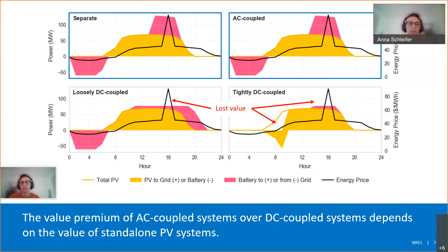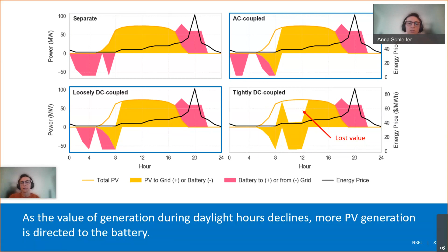And then in the case of the tightly DC coupled system, even more value is lost because the battery has to charge from the PV array instead of from the grid. And sorry, the negative reflects charging of the battery and the positive reflects anything to the grid. So then as the share of PV generation increases, you can see that higher price hours are pushed outside of daylight hours. So now both the AC coupled and loosely DC coupled systems charge later in the morning and discharge in the evening. So now these two systems provide similar value. And then the tightly DC coupled system still loses some value because it has to charge more from the PV during the day.